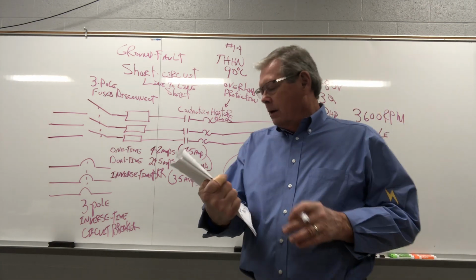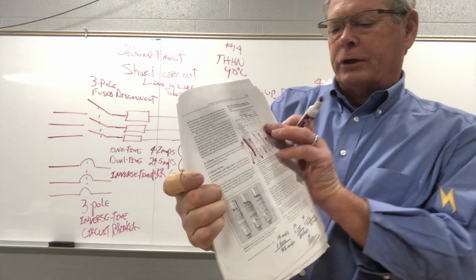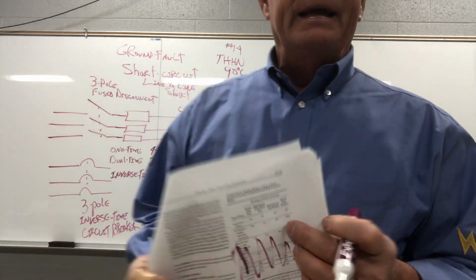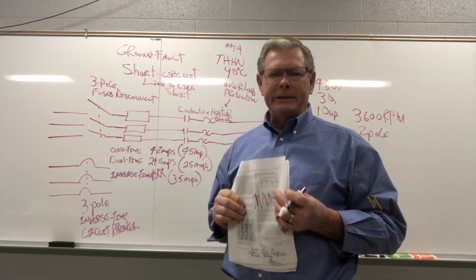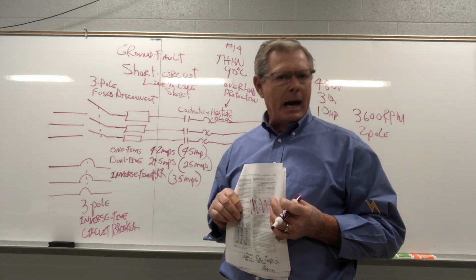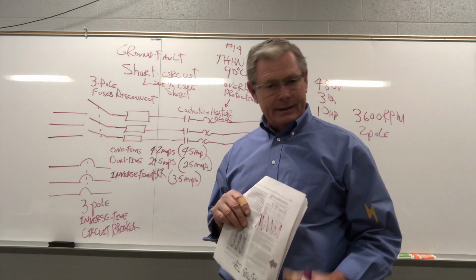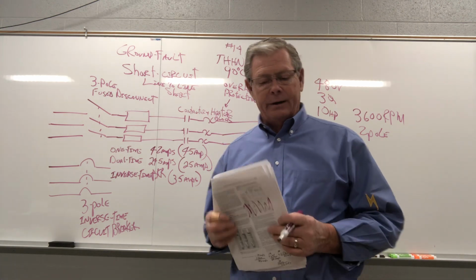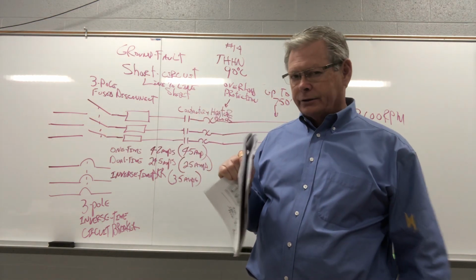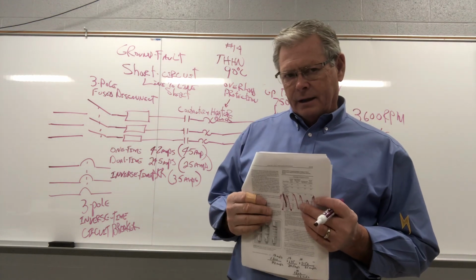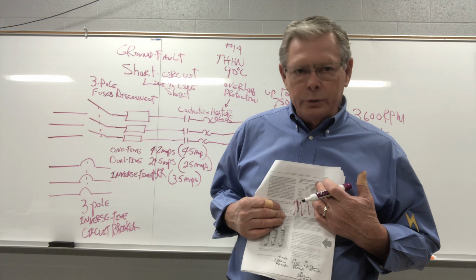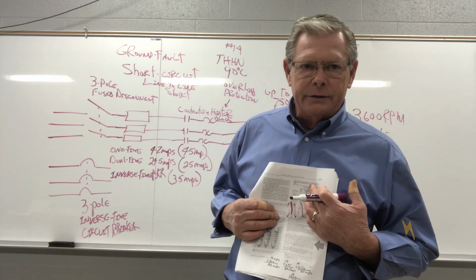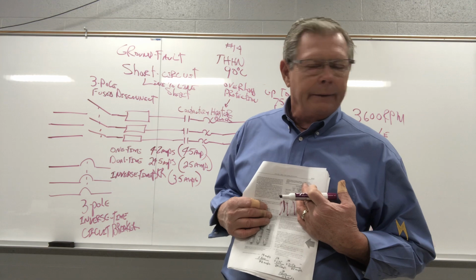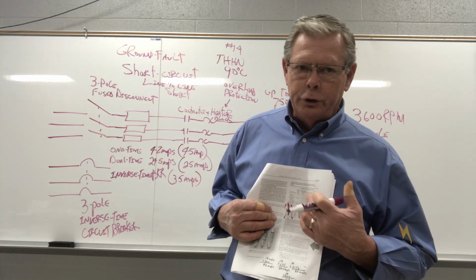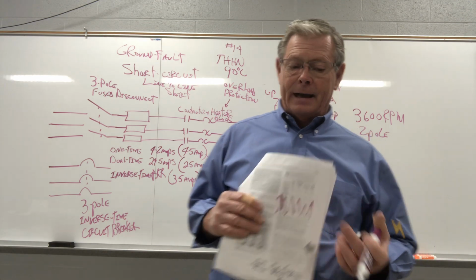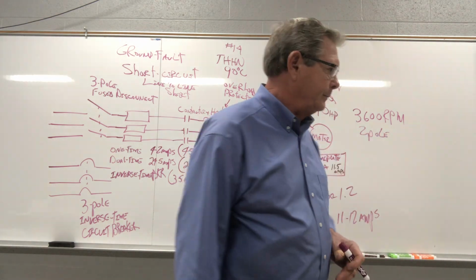Now, you're going to see under inverse time here, where my finger's at, it says 250Z. I spent a lot of time tracking that down. I did not know what the Z meant. I know Z stands for impedance, but it didn't make any sense for a multiplier for a breaker. I looked and looked and looked. Finally, I called someone with the NEC, and that is a typo. You would not believe how many electricians have hunted to try to figure out what that Z was. It ain't nothing, it's a typo. So it's 250, 250%. Now, if you have a breaker, let me show you one.